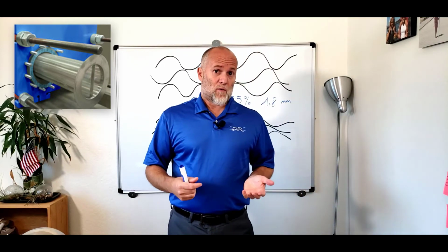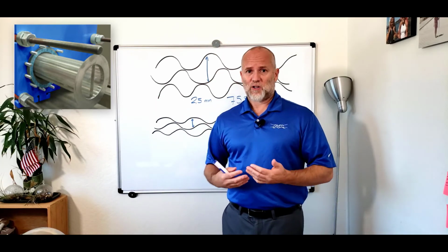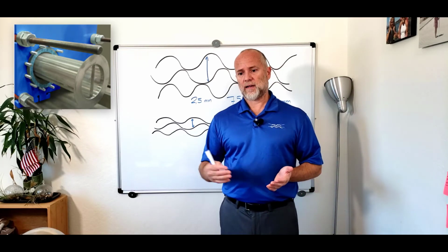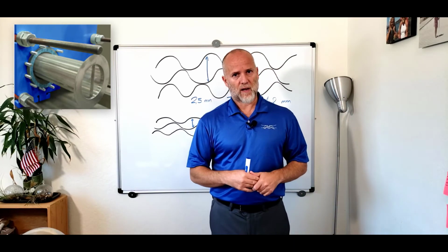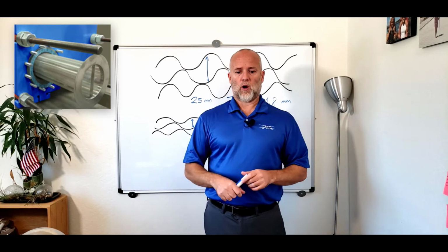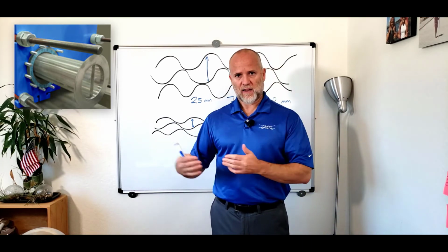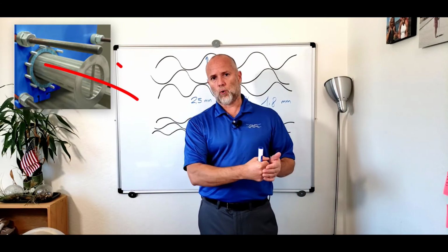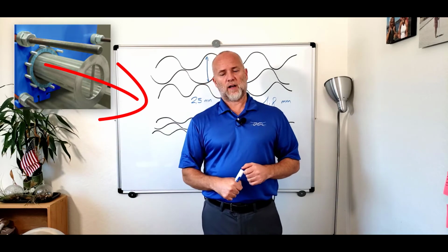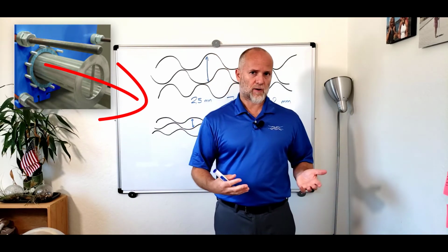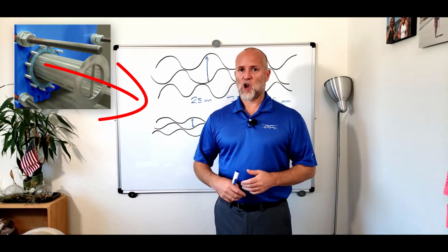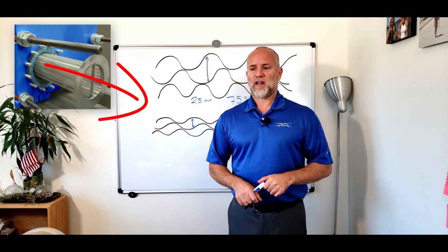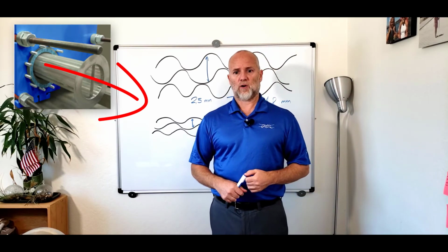In theory, you can have port filters in the four ports, but it doesn't really make sense. You want port filters normally only in the inlet of the cold water coming from the cooling tower, or from the chiller, in any case, the cold inlet. As you can see, you pull the port filter out from the inspection port on the back, so as with a strainer you don't have to disconnect the heat exchanger. Of course, as with the strainer, you have to stop the flow and close the valves. But other than that, it's a minor disruption of your operations.